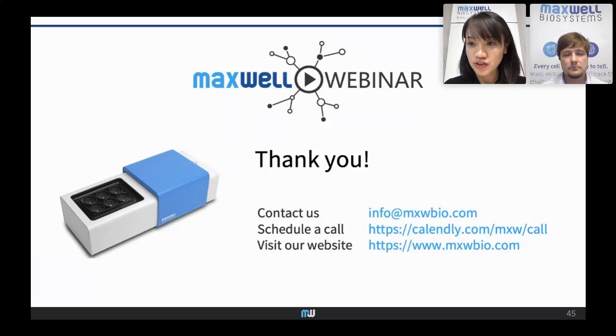Okay, another question related to light stimulation is, does light stimulation induce noise or artifact in the electrodes? So our chips are designed to have very low noise. And as long as the objective that you use on the microscope focuses the light path only on the recording surface and not the adjacent surface where you have the amplifiers, you have very little to no noise on normal photopic levels for retinal light stimulation. Yes, maybe to add on to this, you can also use optogenetics with our microelectrode arrays MaxOne and MaxTwo. So that is an indication that light stimulation is compatible with the system.